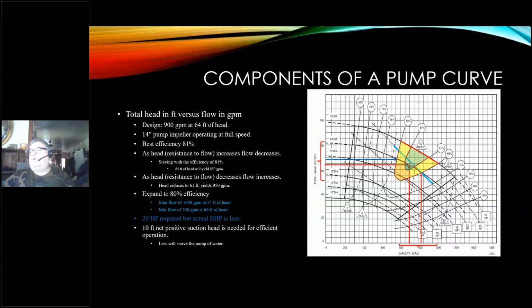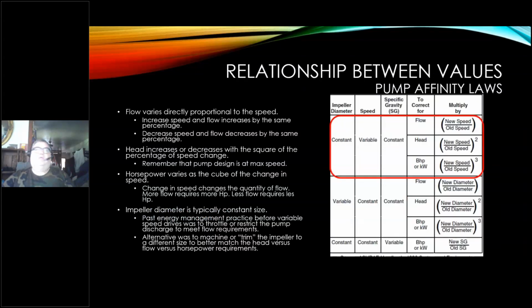20 horsepower, but the actual brake horsepower is going to be less. You'll see that later on. And 10 feet of net positive suction head is needed for efficient operation. Less will starve the pump of water. So again, I have to make sure I see that. I'm sure at some point we've all dealt with the affinity laws. Fundamentally, we take the pump curve and the pump information and apply them to our affinity laws. And this is where we start calculating out where we're going to operate.